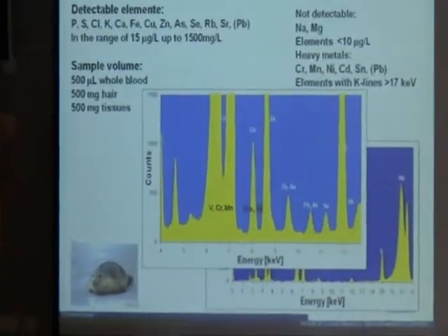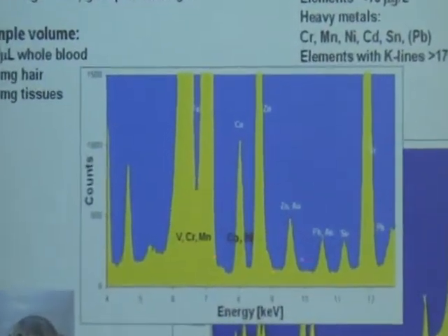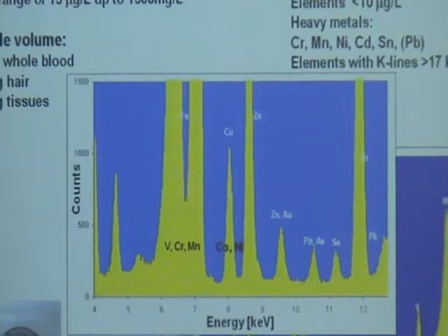And because there's a big iron signal, we could get results for these elements, but they are not reliable, and we don't want to do a real calculation for these trace elements.